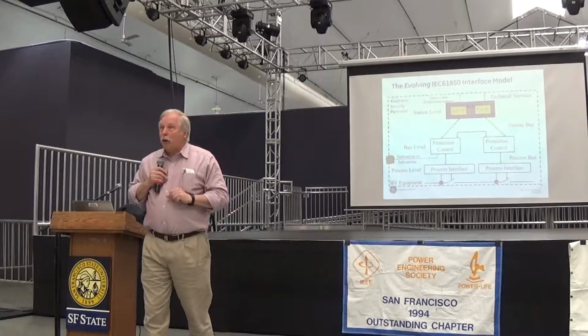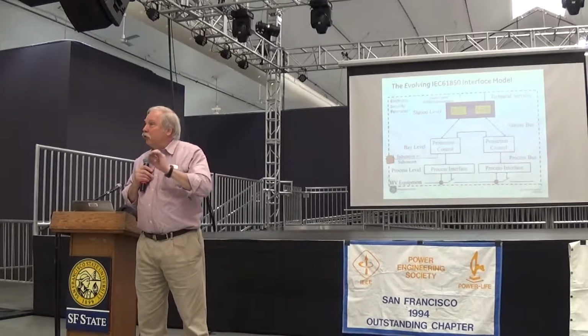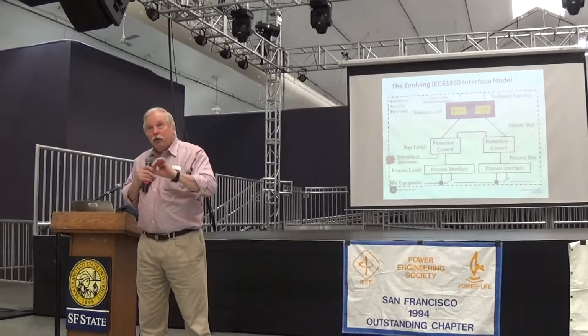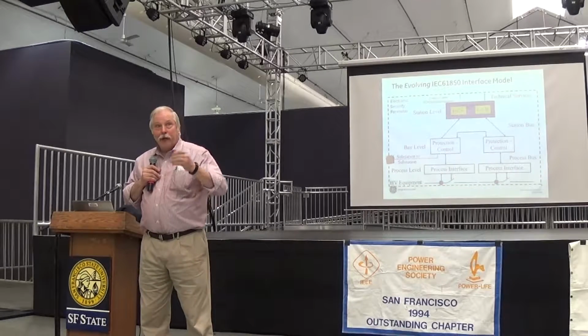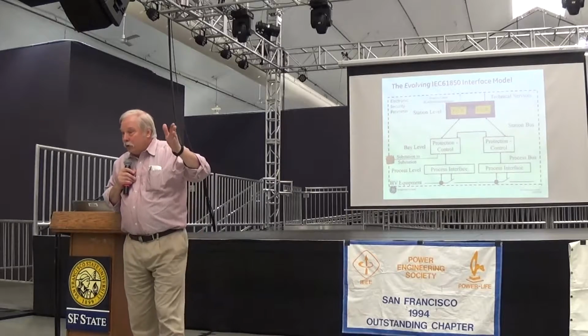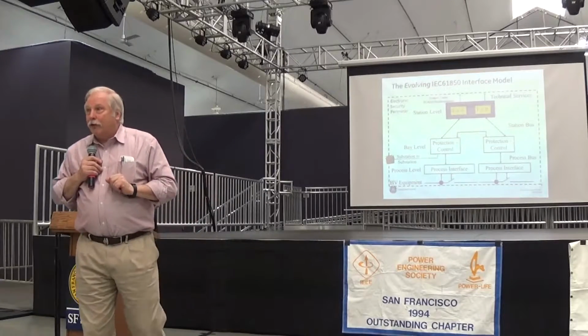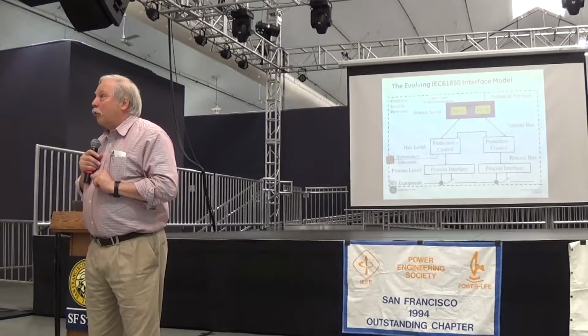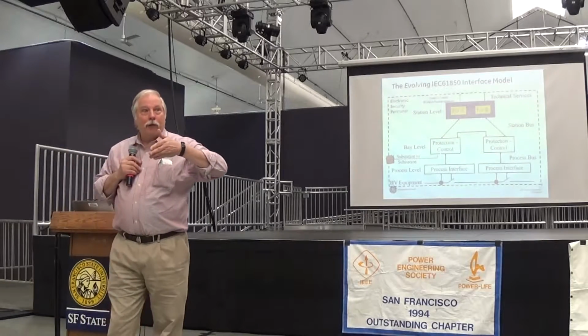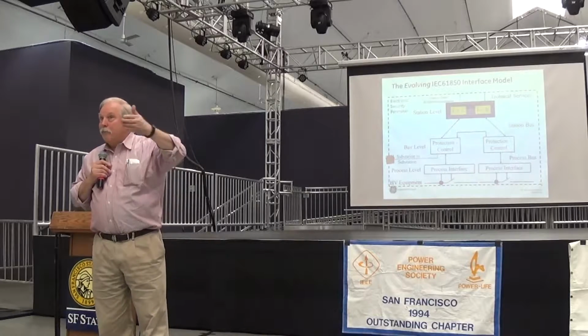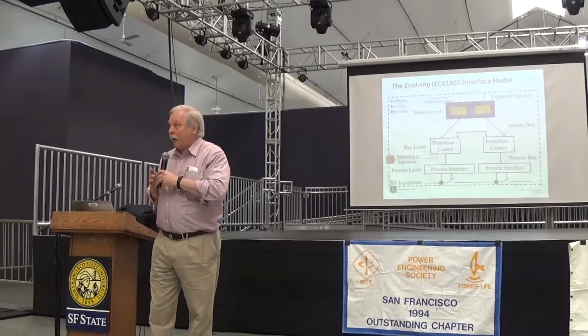A firewall is a mechanism that filters data going into and out of the substation. So devices like the GOOSE message that Alex talked about will not go through a firewall. The firewall kills the GOOSE message. So the question is, how do we get messaging through that firewall?